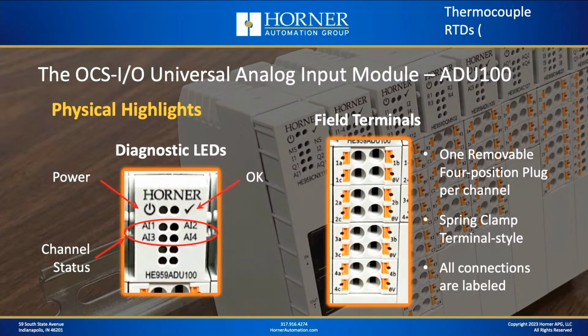Now, from a field termination standpoint, each channel on the ADU100 has 4 terminal connections, an A, B, C, and 0-volt connection. Those plugs are all removable. They're spring clamp style, so you can insert your wiring quickly, and you don't even need a tool to insert if you use ferrules. And all connections are labeled, which makes it easy to wire properly in the plant or in the shop.